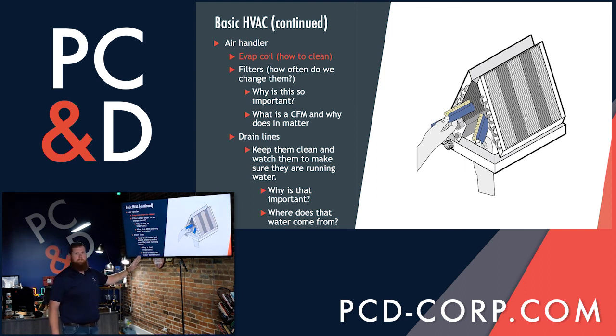But also, we'll say around once a year, we need to dismantle the system, which is simply just a stainless steel cover over the A coil, and we'll have the system turned off, as we don't want any mechanical devices whirling under our arms. We'll apply the solvent on the bottom side of the A coil as the air is being pushed up. That's the area that will catch all the dust and debris. And again, as depicted, we'll scrub those areas clean. Once finished, replace the system and return power to the system.